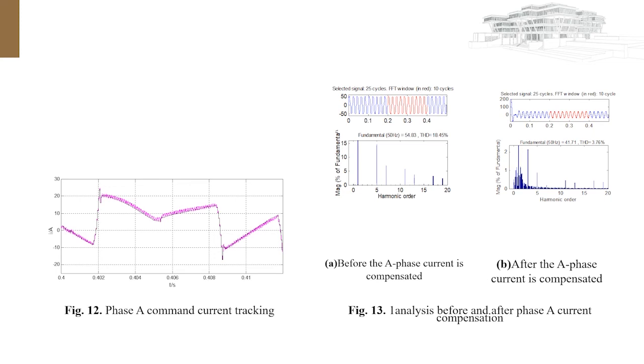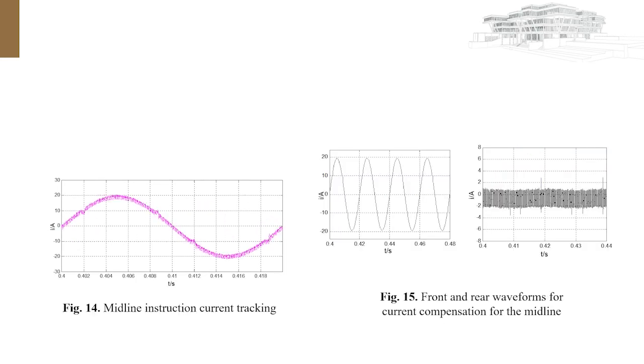Figure 12 is the case where the APF phase output current tracks the phase command current, and Figure 13 shows the compensated current before and after the power supply. As can be seen, the supply current after APF compensation is basically a sine wave. The total harmonic distortion rate of the supply current was reduced from 18.45% before compensation to 3.76%, and the current harmonic component was effectively suppressed. Figure 14 is the APF fourth-leg output current tracking the middle command current, and Figure 15 shows the front and rear middle command current after compensation.